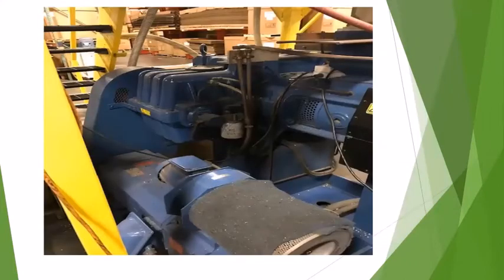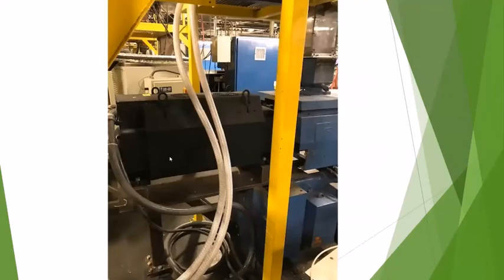I'm going to go into a couple of things that I've been involved in also that you might want to be aware of. This happened to be an extrusion machine in New England that I was working on that had a 75 kilowatt DC motor going through belts into the gearing. And what we had installed are these new square frame high torque motors that actually have a very unique rotating field in them.